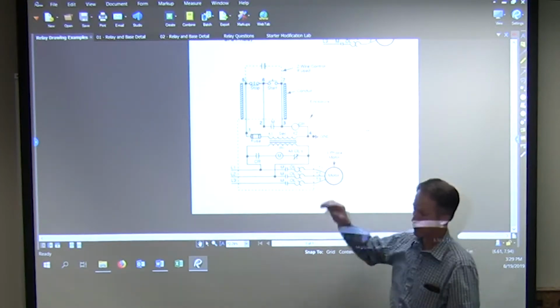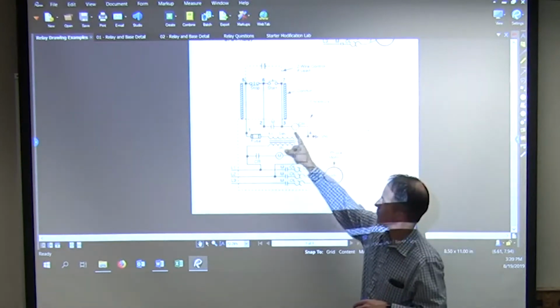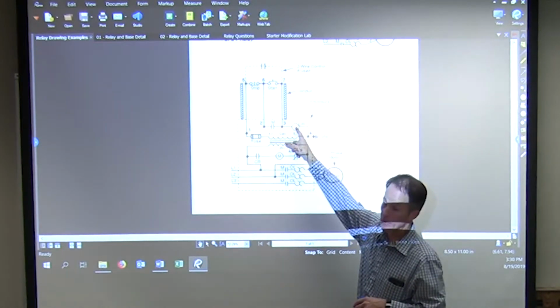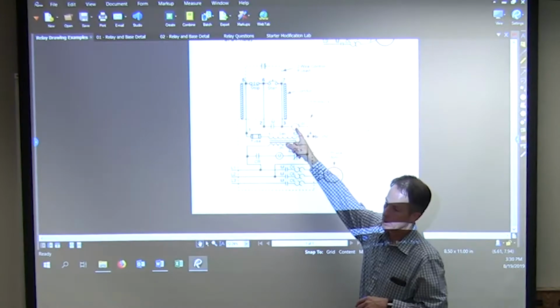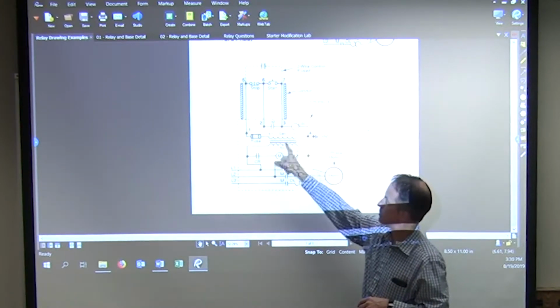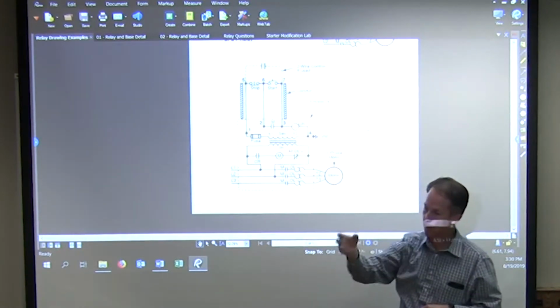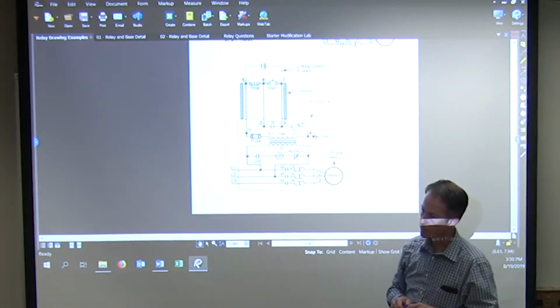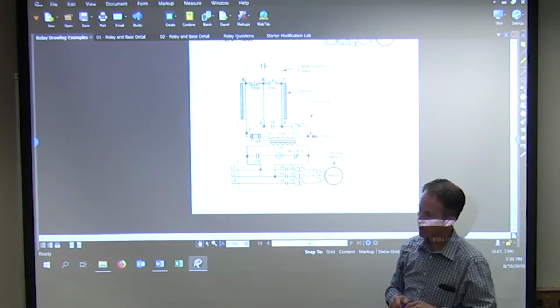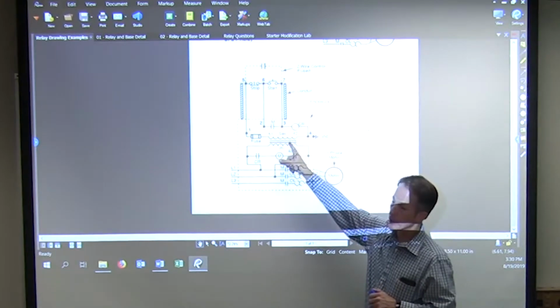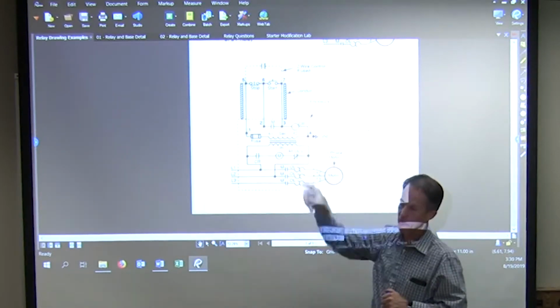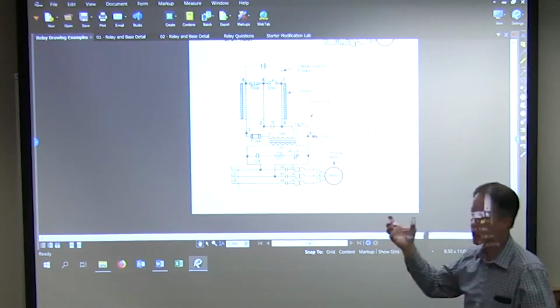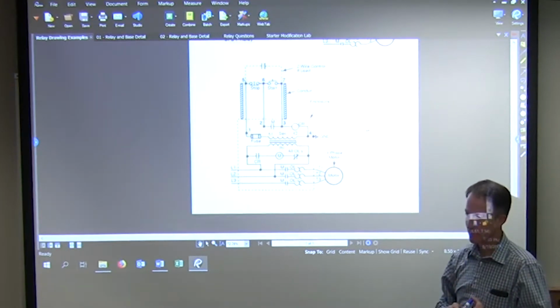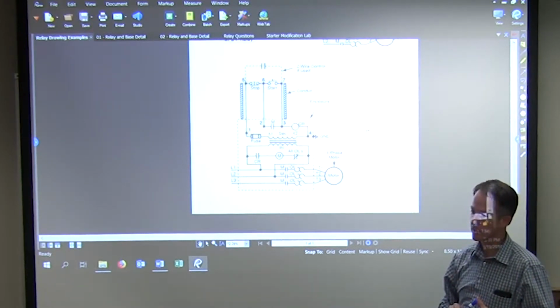Okay, so when I'm sizing this transformer, it's based on this load or the inrush of that load. And that's really all that matters. This transformer may have some heat. You just said though, you could potentially need a 5 amp fuse based upon the load. It depends on this transformer, right? That's what I just said. Okay, so you said the same thing. So the size of the transformer is what determines the fuse.